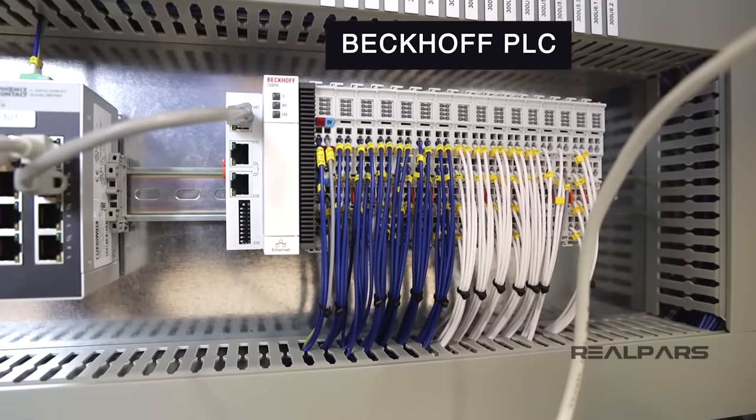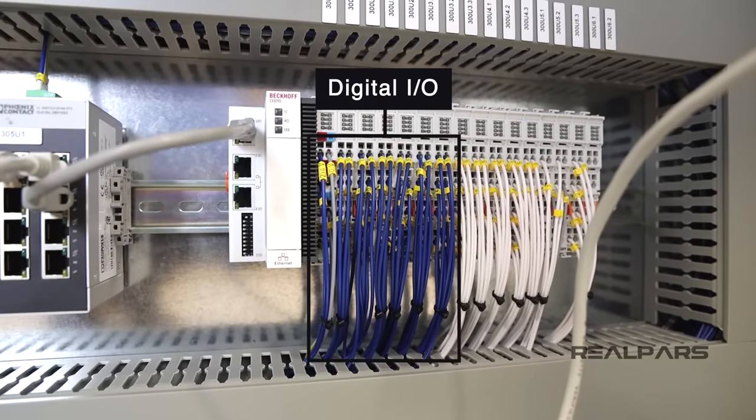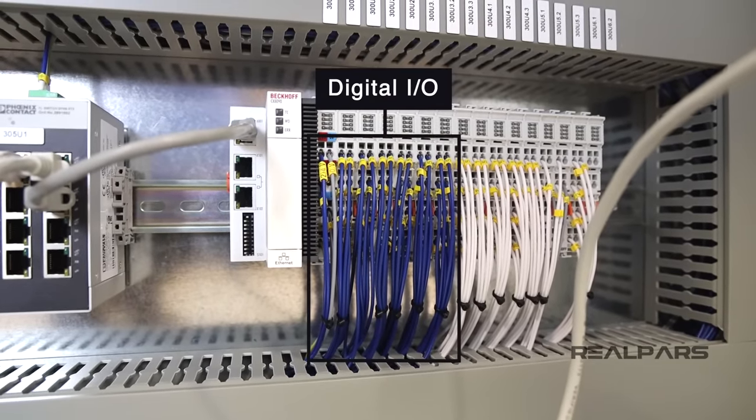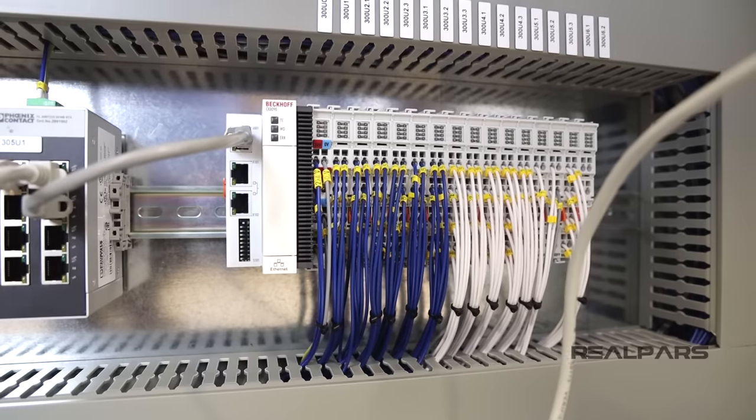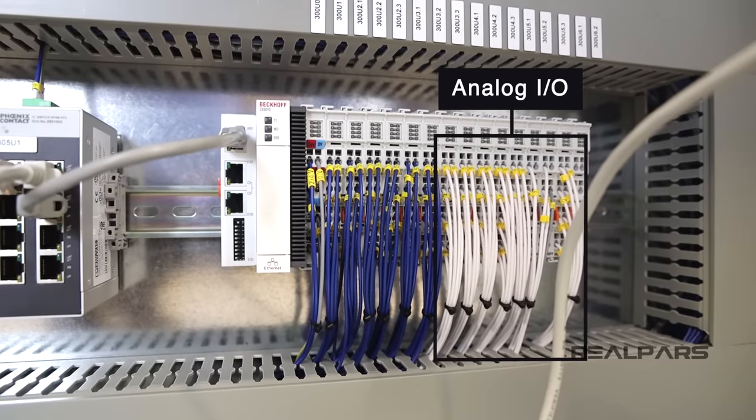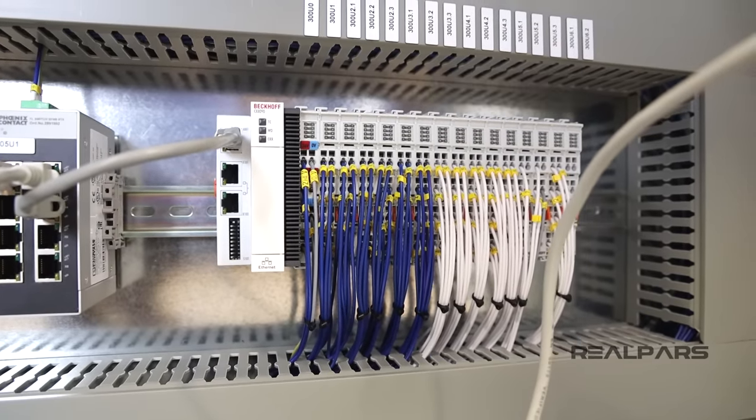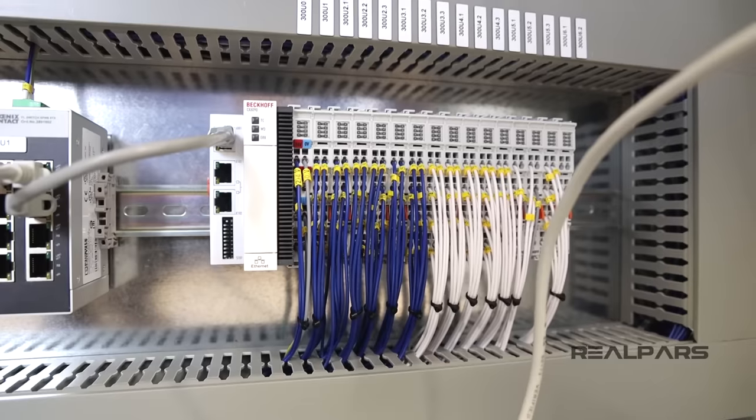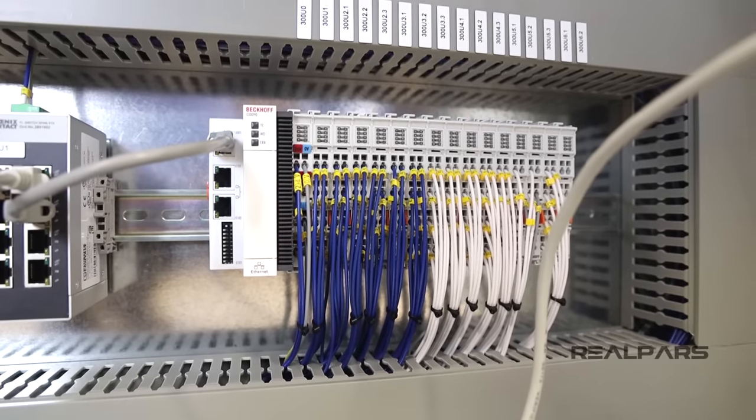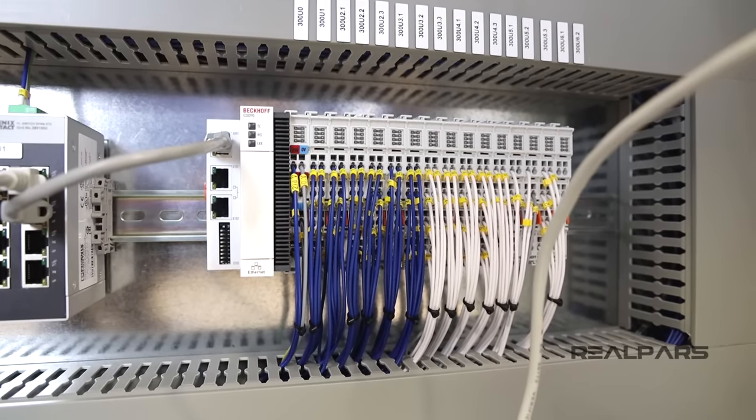On the back of the door, you see that the switch is wired all the way to the PLC input. This is a Beckhoff PLC. The blue wires that you see here are digital input and output signals, the white wires are analog inputs and output signals. These wires come all the way from the sensors and actuators in the field and get connected to the PLC.